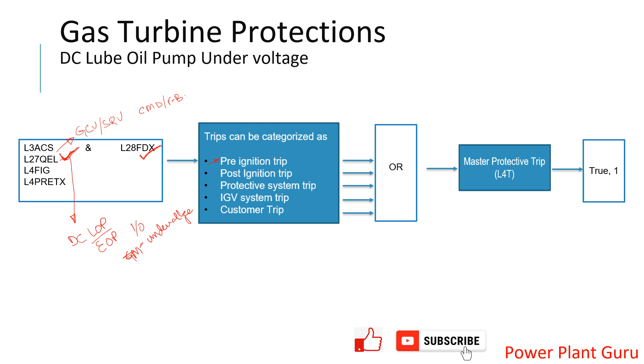EOP healthiness from the electrical system is being checked. For some of the latest machines, EOP is given a start command and it runs for around 30 seconds, with a health check including pressure and other parameters. For older machines, only GT MCC under-voltage was checked. You may find either of these combinations in your plant — both are ways to ensure the machine's emergency oil system is healthy before starting.